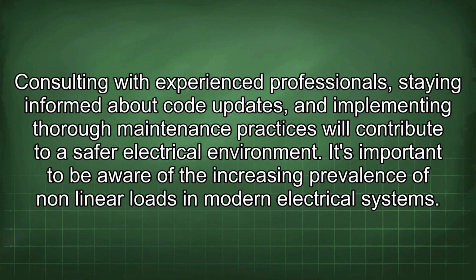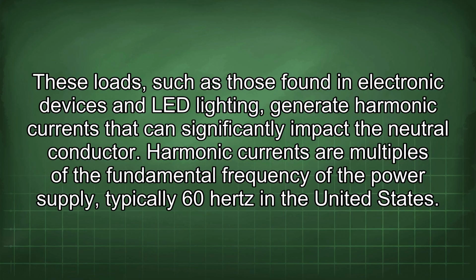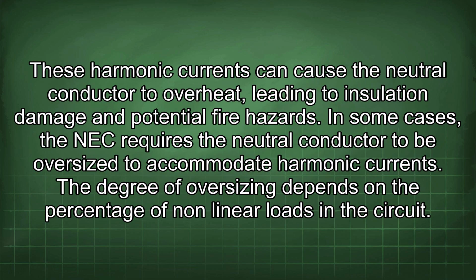Consulting with experienced professionals, staying informed about code updates, and implementing thorough maintenance practices will contribute to a safer electrical environment. It's important to be aware of the increasing prevalence of nonlinear loads in modern electrical systems. These loads, such as those found in electronic devices and LED lighting, generate harmonic currents that can significantly impact the neutral conductor. Harmonic currents are multiples of the fundamental frequency of the power supply, typically 60 Hz in the United States. These harmonic currents can cause the neutral conductor to overheat, leading to insulation damage and potential fire hazards.